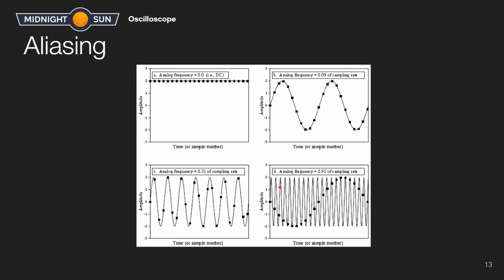And then as the frequency increases, and it's relatively high compared to the sampling rate, you can actually see that the samples look like a completely different waveform than the original wave. So just be aware that high frequency components may get distorted or may not look the same as what the actual signal is. And this is a function of the sampling rate of the oscilloscope and also the memory.